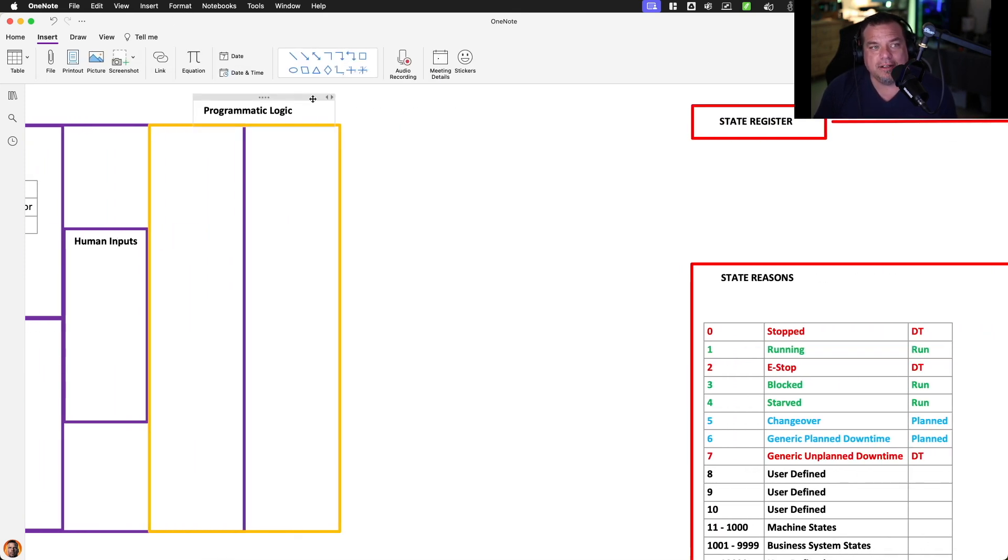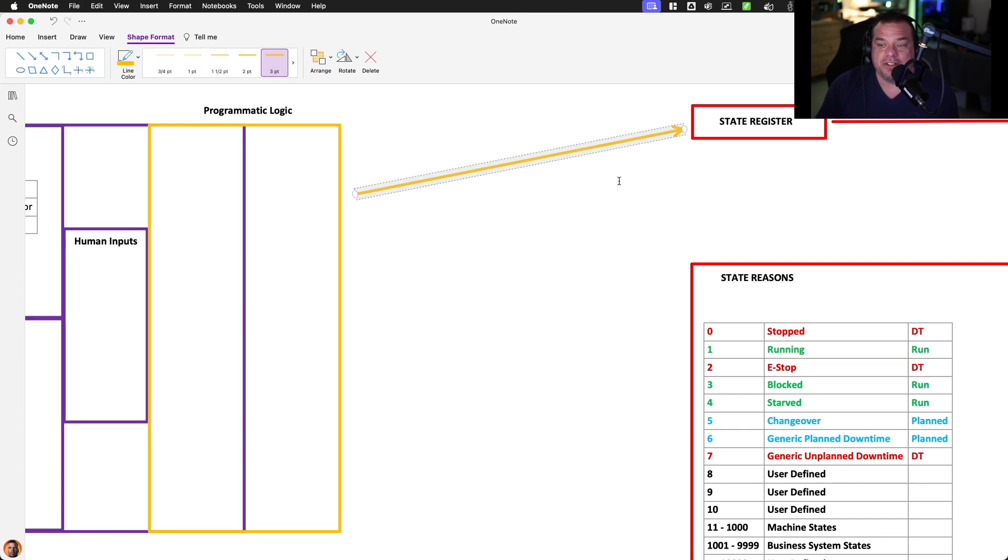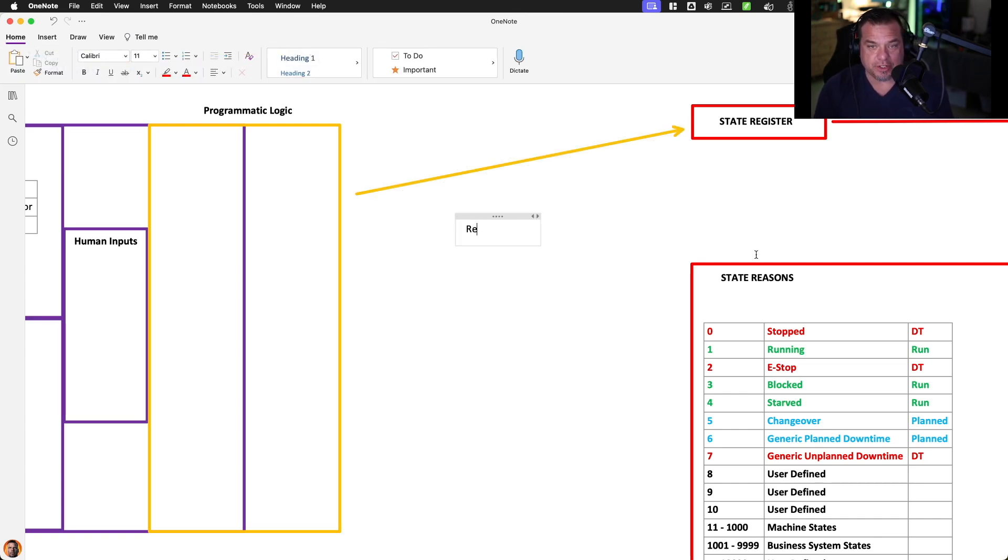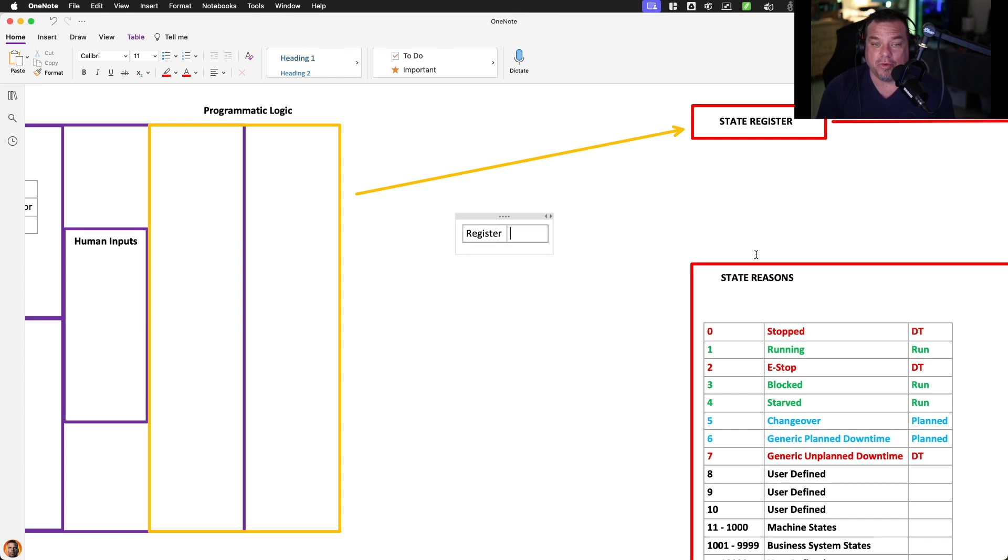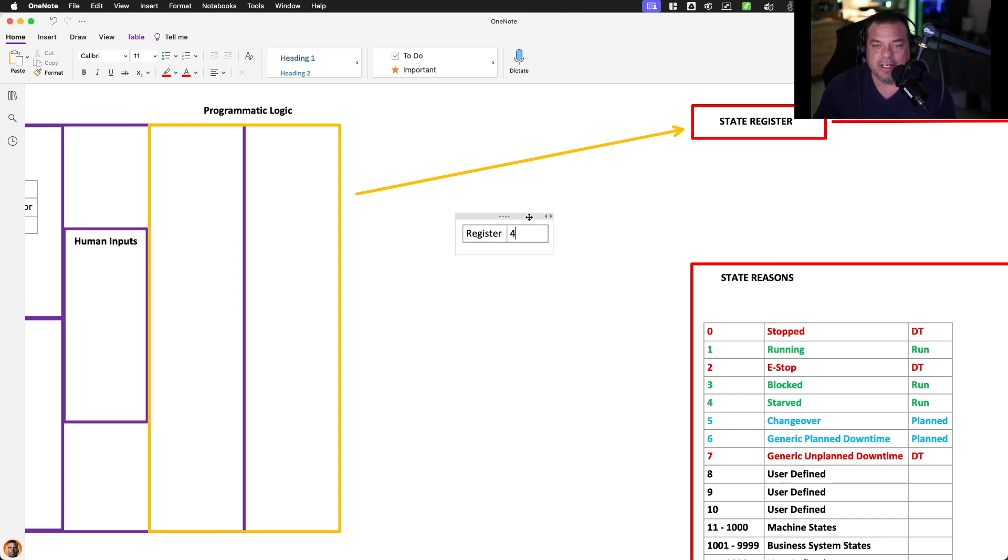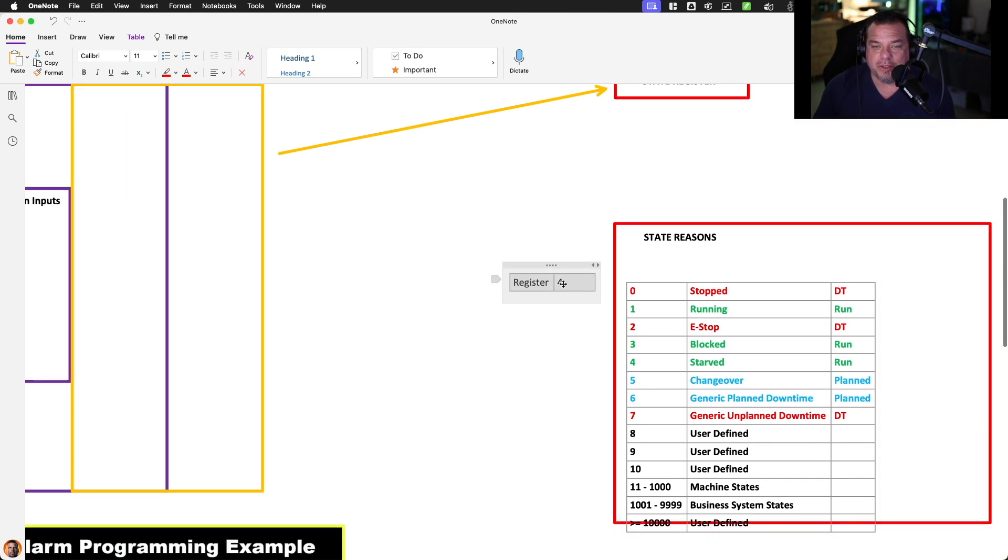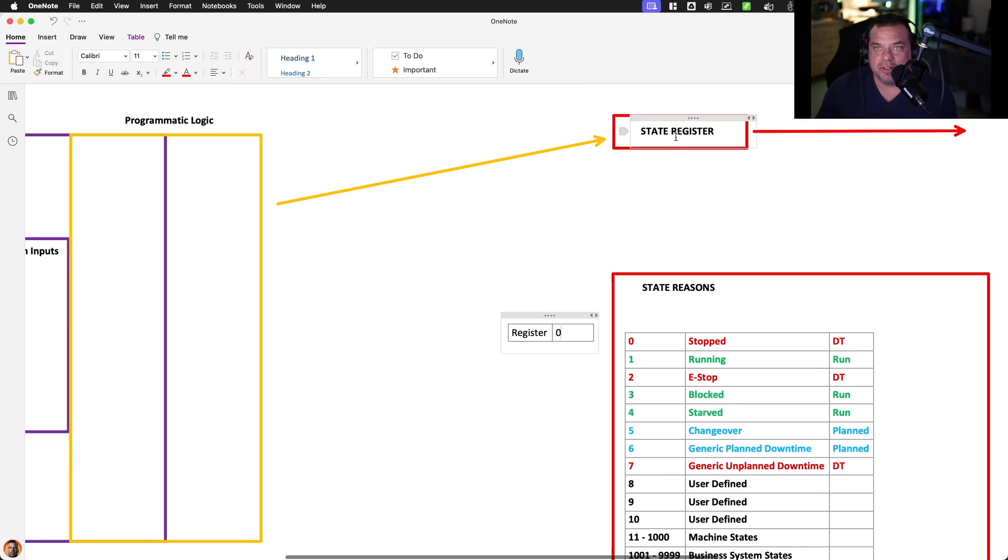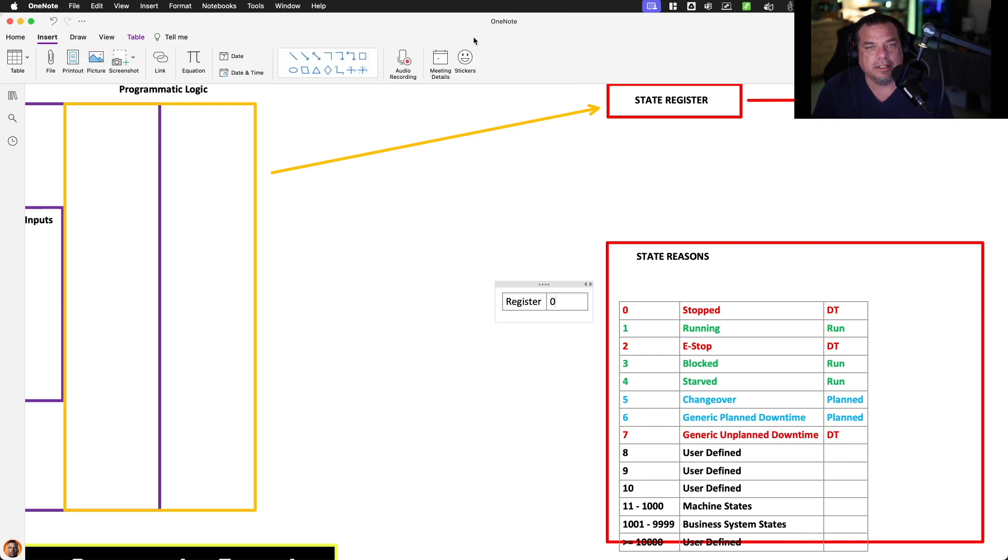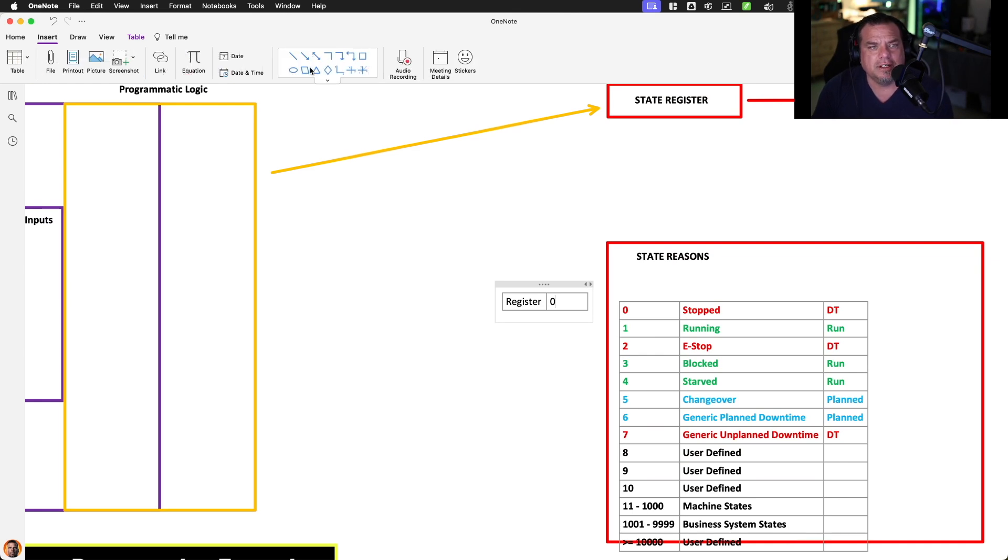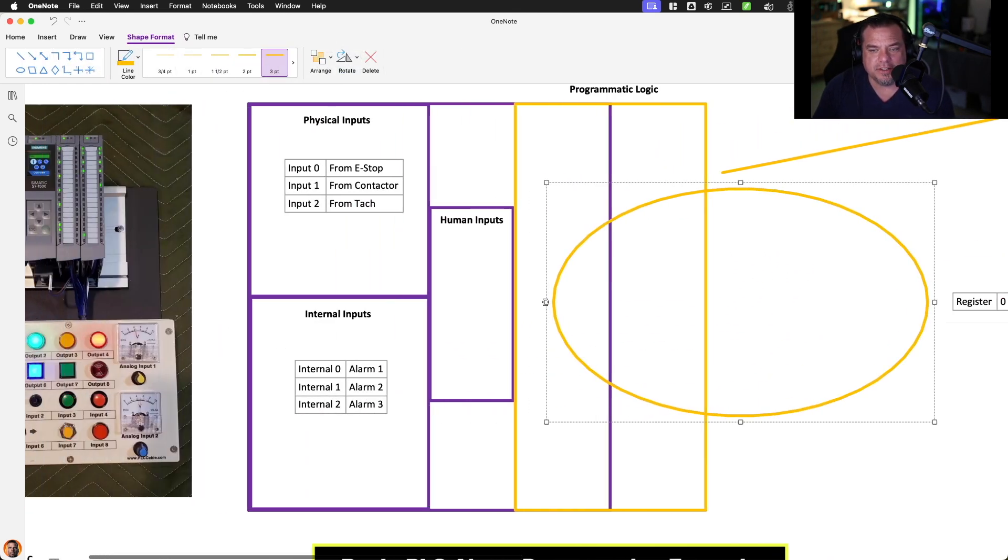And it generally is going to look like this. We're going to try and create a state register. So that is a one value, one register that is going to give us a value. It's always going to show a value, it may show zero, it may show one, it may show two, it may show three, it may show four. And what we're going to have is a lookup table where if the value is zero, if the register value is zero, then that's going to mean that the line is stopped. We're going to take logic, we're going to write logic, that's going to use all of these things.